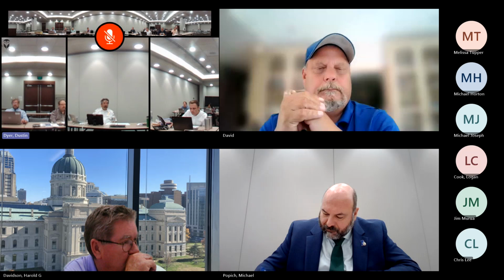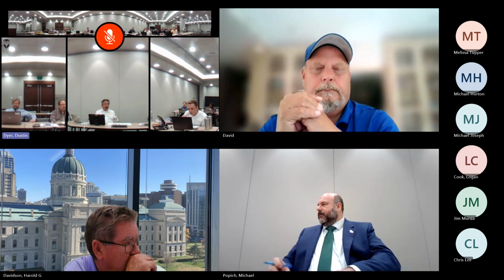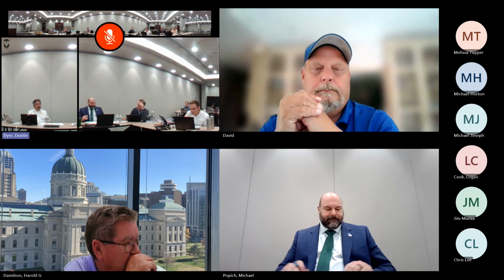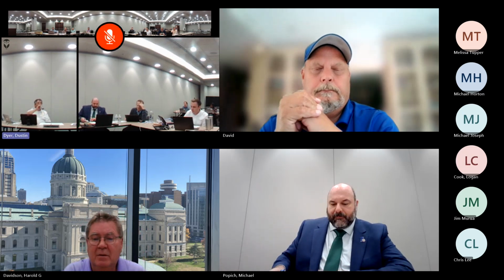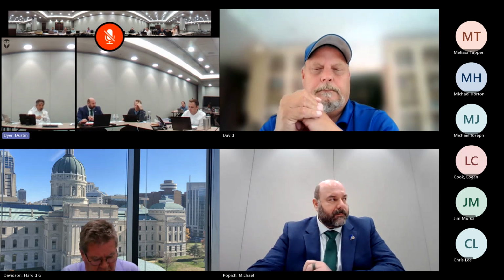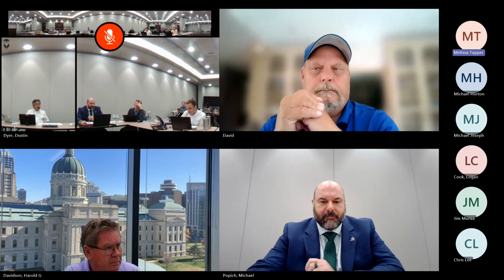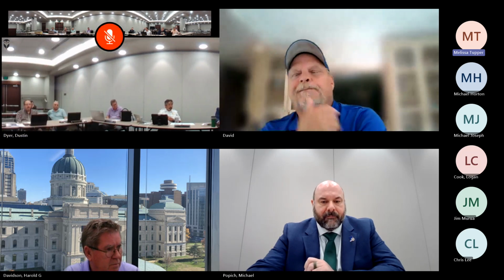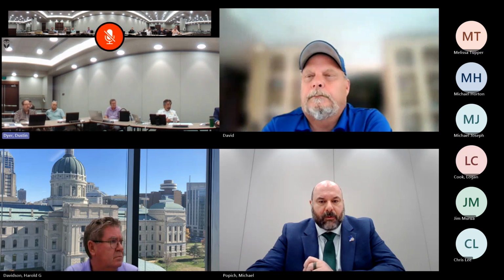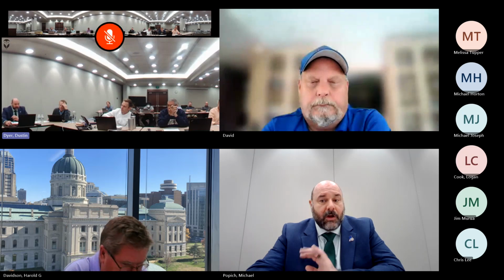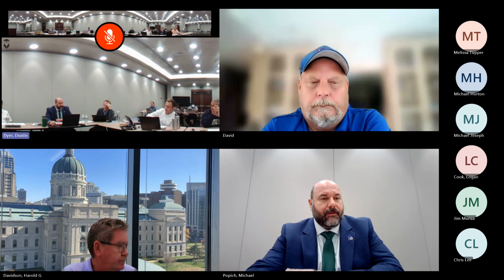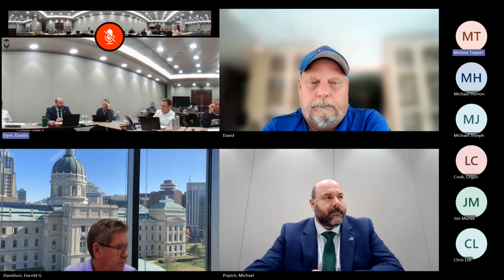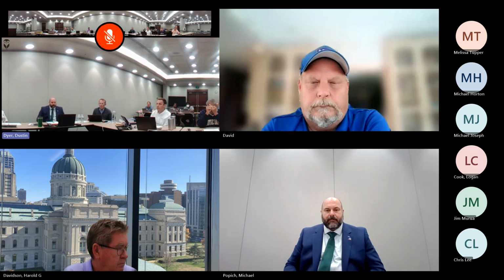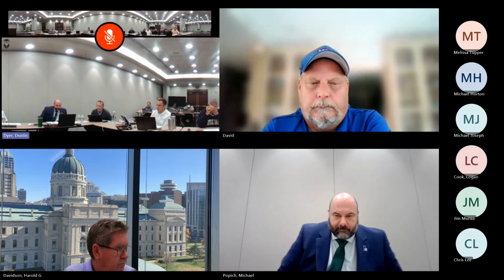It's both, right — the occupant load, yeah. So you have 300, maybe 307 that they could potentially put in there. They gave them a calculated occupant load, yes. But that was only one of the two checkboxes — it was over occupant load but still under 5,000. No, it's both, because the mezzanine adds to the fire area, so they're over 100 people and over 5,000. Before the addition they were at 35; right now they're at 4947 for the first floor and 792 in the mezzanine — that's with the addition. The addition drops the first floor down to about 4,000 current space, fire area.